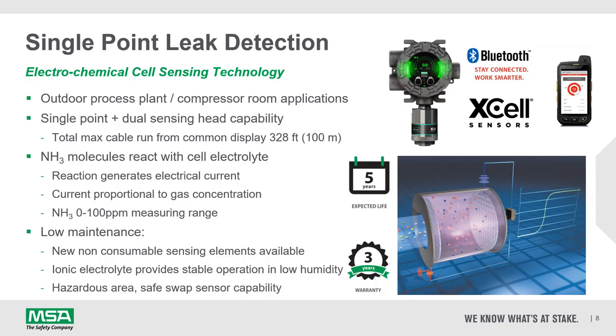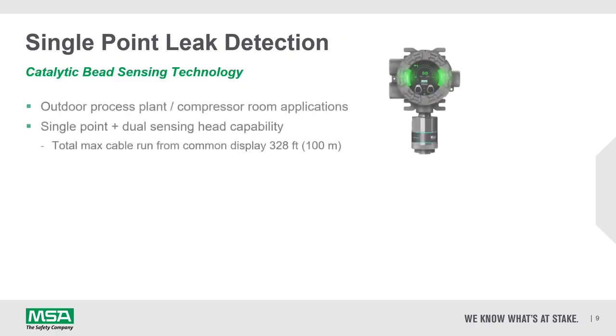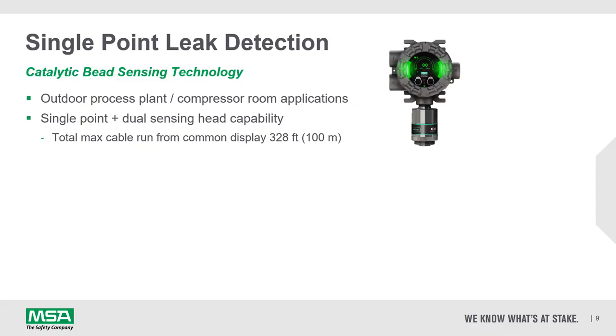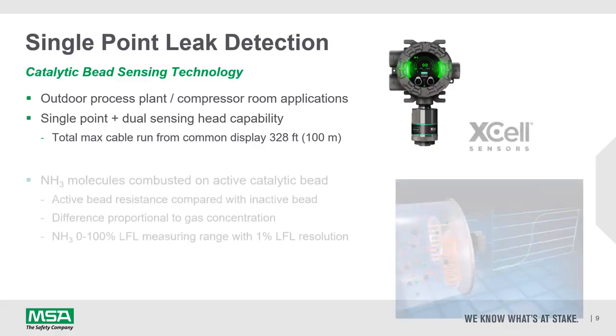When needing to change the sensor and its element, it is now possible to do that in a hazardous area without declassifying it by using what is called a safe swap technique. Single-point ammonia leak detectors using catalytic bead sensing technologies are used in similar applications. They're also available in a dual sensing head format, saving cost by only having to utilize a single display.